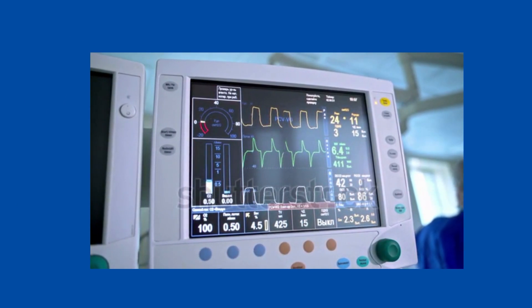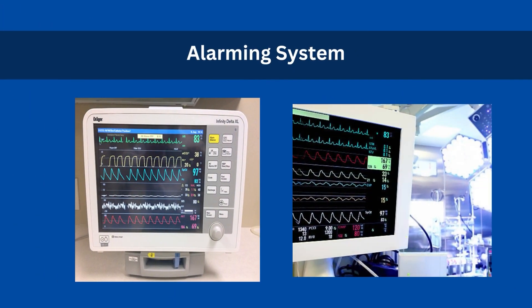The machine starts alarming whenever there is less oxygen supply than required. For example, some machines have a limit of four liters of oxygen — whenever it falls below four liters, the machine shuts itself down and ceases all functions. For such conditions, we always have emergency cylinders in the OT. The machine also alarms and changes its beeping sound whenever there is a fluctuation in vitals or any issue with the oxygen probes or ECG electrodes.